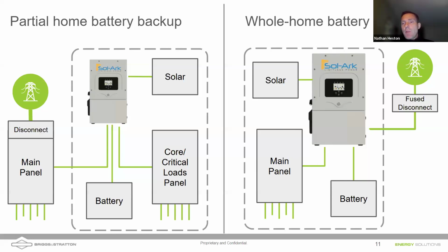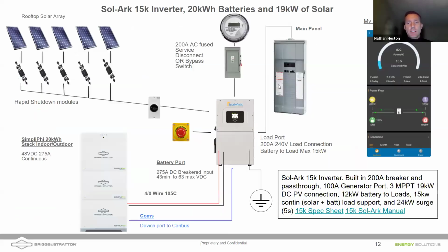And so we do this by having a large pass-through of the inverter. So for example, the Sol-Ark 15K has a 200 amp pass-through, so you can feed all 200 amps through the busing, the AC busing, and the relays on the inverter and into the main load center of the house. The battery system, in a grid outage, can keep the loads alive, and solar can also support those loads and charge the batteries. Additionally, you could have AC coupled solar, or you could integrate a generator into this type of scenario.